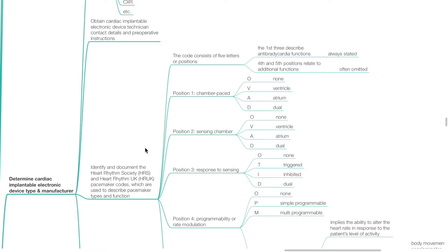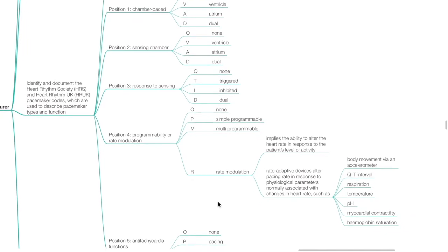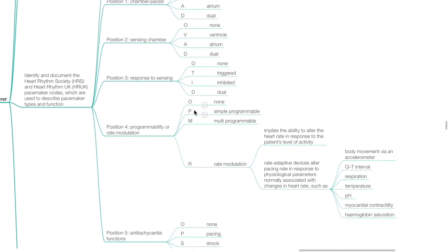Position 1 — chamber paced — may be O (none), V (ventricle), A (atrium), or D (dual). Position 2 — sensing chamber — may be O (none), V (ventricle), A (atrium), or D (dual). Position 3 — response to sensing — may be O (none), T (triggered), I (inhibited), or D (dual). Position 4 — programmability or rate modulation — may be O (none), P (simple programmable), M (multi-programmable), or R (rate modulation). Rate modulation implies the ability to alter the heart rate in response to the patient's level of activity. Rate adaptive devices alter the pacing rate in response to physiological parameters such as body movement, QT interval, respiration, temperature, pH, myocardial contractility, and hemoglobin saturation.